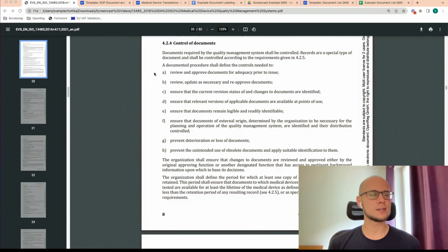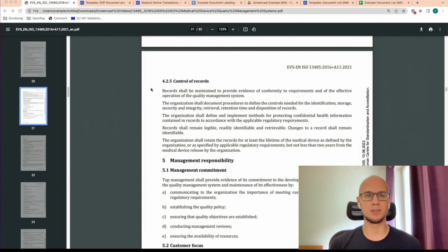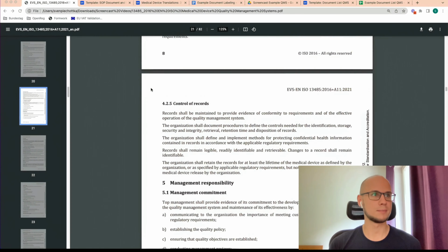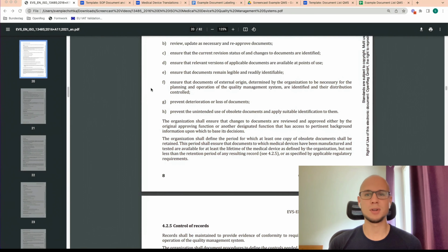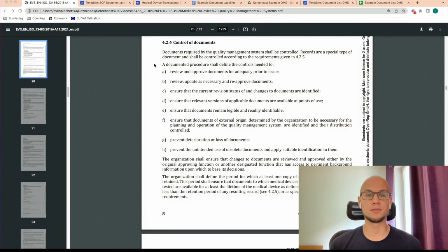Whatever solution you go with, make sure you read up on the requirements and check if your solution is compliant. As always, we will therefore start with a look at the regulatory requirements. ISO 13485 paragraph 4.2.4 and 4.2.5 are your point of reference. They are formulated in a pretty tangible and practical manner, I would say. I'll just pick out a selection of the most important ones in my view.